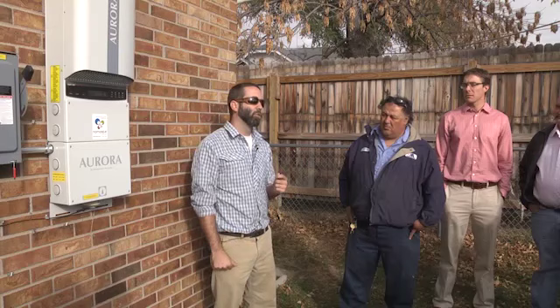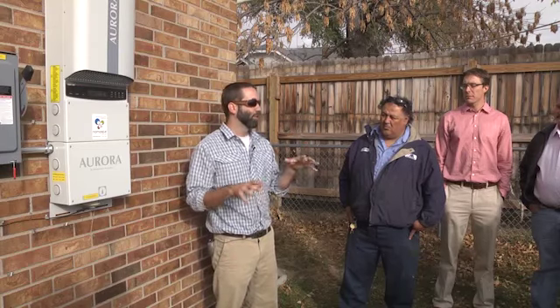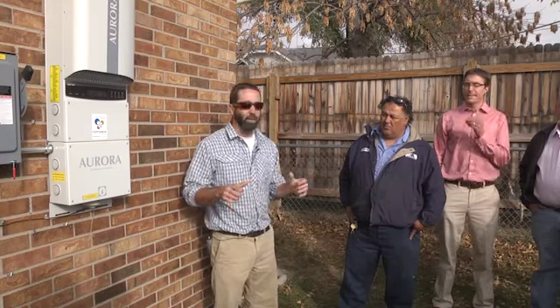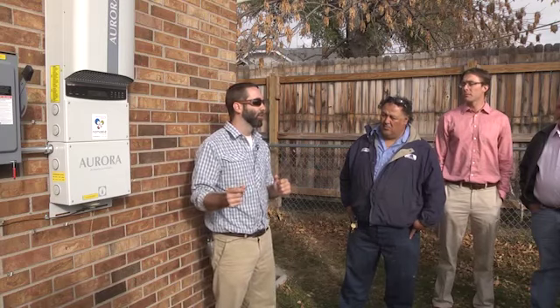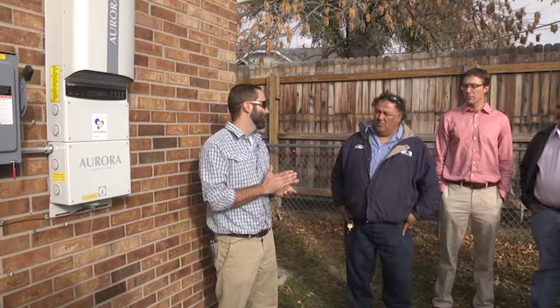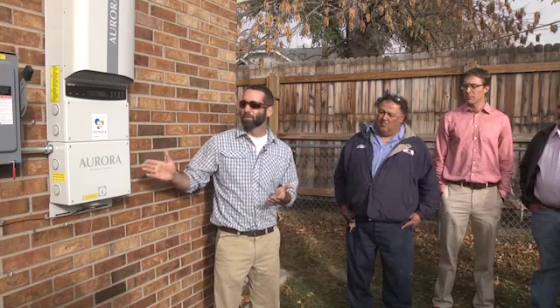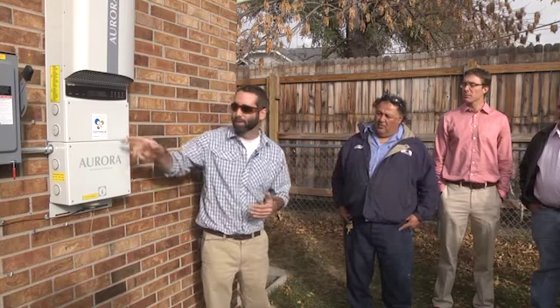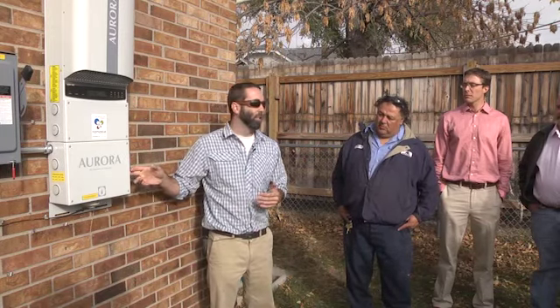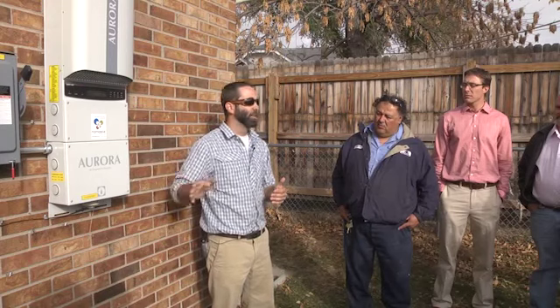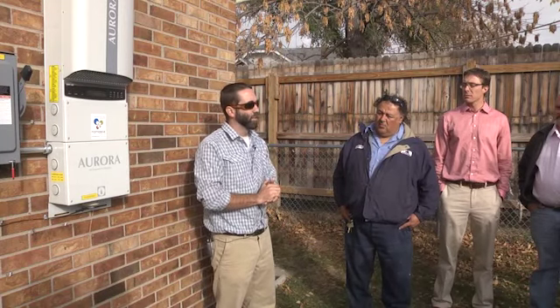Basically, when the grid voltage goes away, for example if the transformer feeding this neighborhood blows up, the inverter immediately notices. The inverter needs grid voltage to function, so if it loses grid voltage for any reason, it turns itself off. It basically slams the door between the DC and AC sides of the box, and there's a very specific reason it does that.